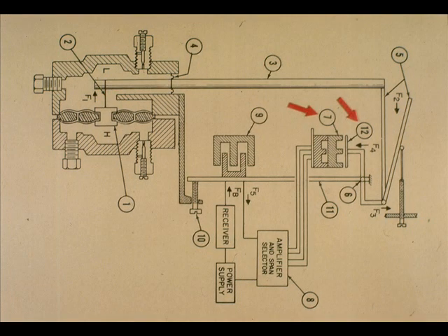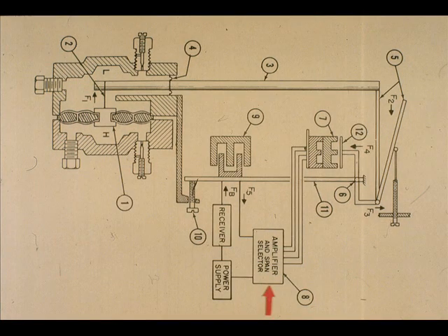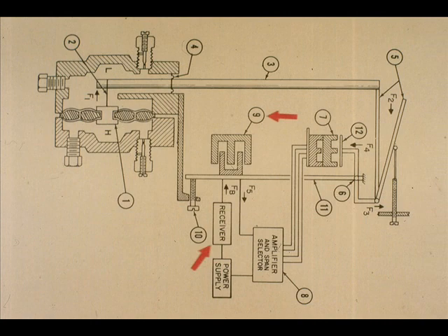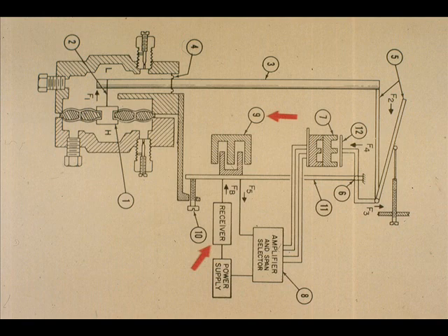The ferrite disk 12 is part of a differential transformer 7, which serves as a detector. A position change of the ferrite disk changes the output of the differential transformer, which is fed to the oscillator amplifier section 8. The oscillator output is rectified to DC and becomes the 10 to 50 or 4 to 20 milliamp transmitter output signal.